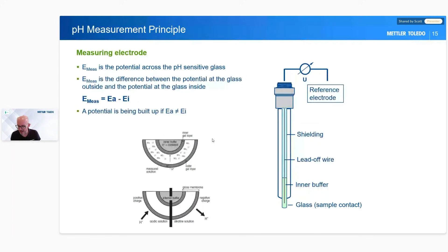The most common question I get is, when I'm using pH, I'm only sticking one electrode in. That's because, due to advanced manufacturing techniques, we're able to take the measuring electrode and the reference electrode and put them into one electrode. We generally call this a combination electrode. Sometimes you might see that it says combination electrode, and that's because we've taken both electrodes and pushed them together into one piece.